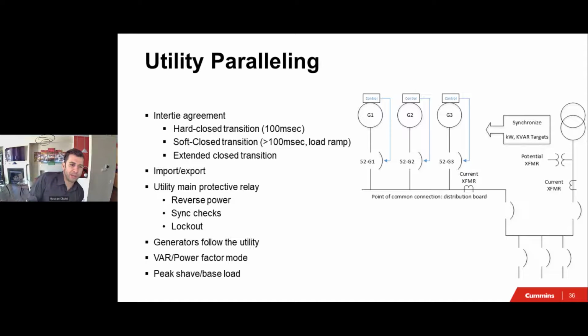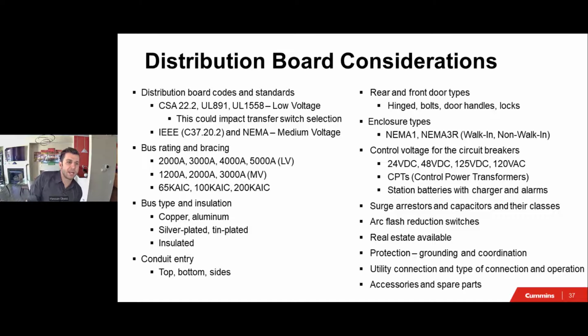I have 3 more slides, and then we'll turn it back to questions. The next 2 slides are for when you're designing a system. I just want you to use this as a checkpoint. When you're specifying paralleling gear, whether it's 1558 or 891, use this as a checkpoint to make sure these points are not missed. For example, whether it's CSA, UL, 891, 1558, the bus rating, the insulation, conduit entry, whether the doors are rear or front, hinged, are there door handles, enclosure type, if you need arc flash protection, what is the control voltage? Is it 24, 48, 125 DC, 120 AC? Are we using CPTs? We have to think about those.